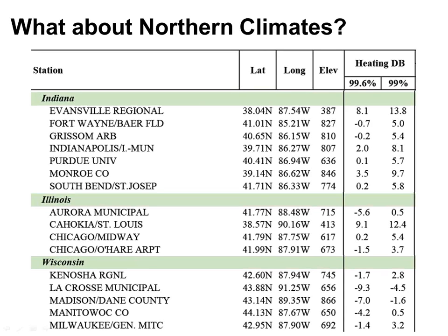All right, so what about northern climates? When we start talking about northern climates, the first thing we got to do is figure out, well, can we even use a heat pump in these climates? So specifically, I'm looking at Indiana, Illinois, and Wisconsin because that's where the majority of you guys are from on this webinar. And right now what I'm looking at is the ASHRAE Fundamentals Handbook 2013 edition and the weather data specifically on the heating side of the equation.